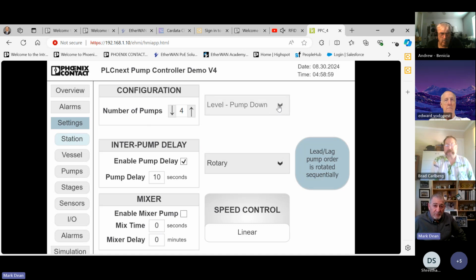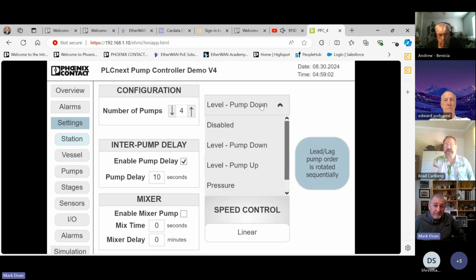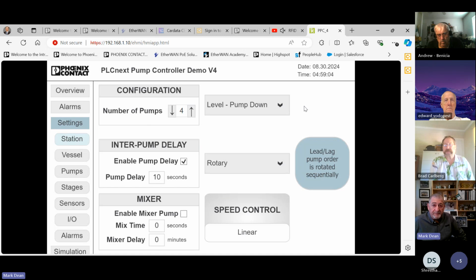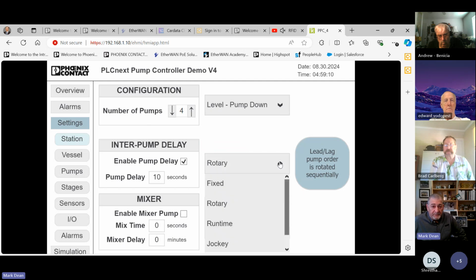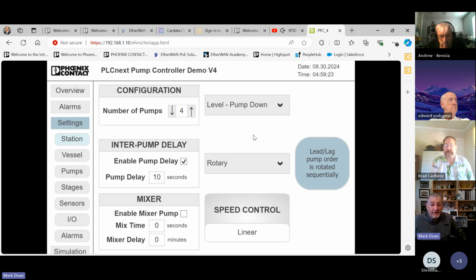The application we're running is pump down, so it could be a pump up or pump down with the PPC 2.0. When using multiple pumps, you might want them to rotate, or you might want them fixed. Maybe you want them to start the next one with the lowest amount of runtime, so we balance our hours on the pumps. All that is available right there.